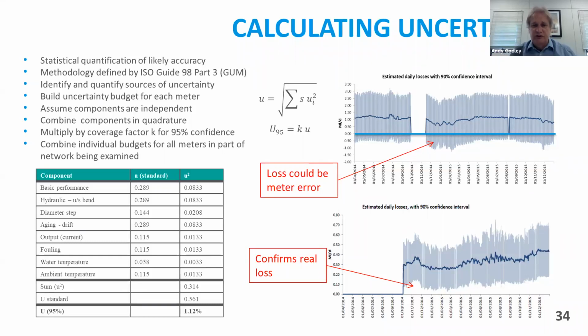And we use that information to build an uncertainty budget for each meter. And we would do this for each individual meter, and uncertainty budgets can take several different forms, but there's an example there at the bottom on the left. So all the different components of uncertainty, so the underlying basic performance of the meter that comes from the manufacturer's specification. In this example, we know that there's an upstream bend, so there's a component due to the hydraulic conditions. We don't necessarily know how that bend is affecting that meter, but we know it's having some effect, and we know approximately the magnitude of that effect, so we can allow for that. We can look at things like aging. We know how old the meter is. We can make an allowance for that. And all the different parameters we can make allowances for based on what published information we've got.